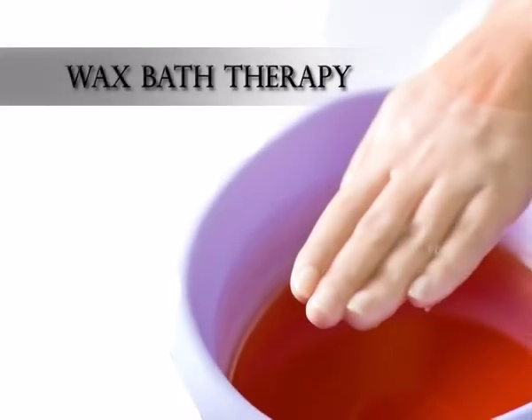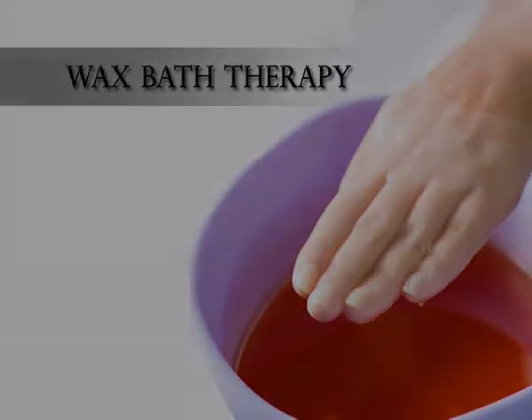And the next topic comes wax bath therapy. The paraffin wax melts at around 54 degrees Celsius, but this point can be lowered by addition of mineral oil such as liquid paraffin. Most wax baths are kept at temperature between 42 to 52 degrees Celsius, often at a higher range for hand treatment and rather lower for the feet. The wax is maintained molten in stainless steel or enamel bath, which are electrically heated. Temperature is kept constant by the thermostat.